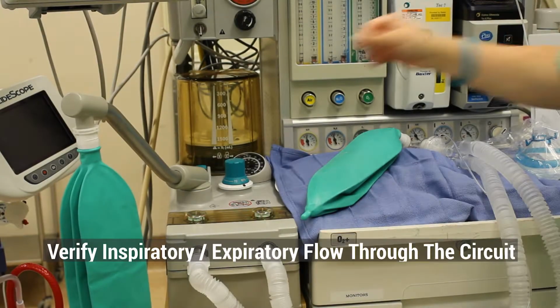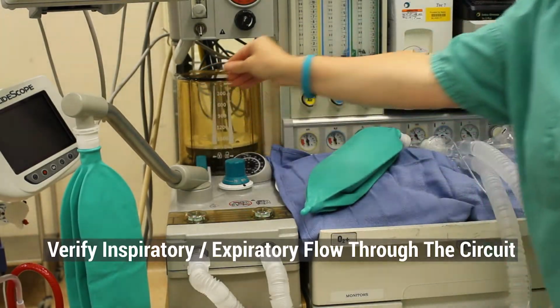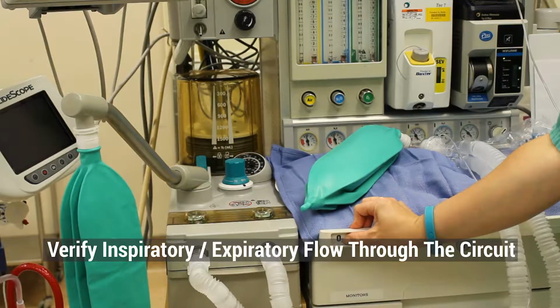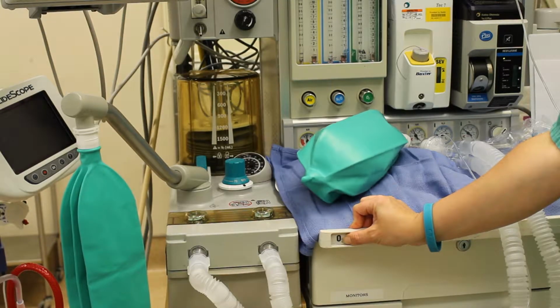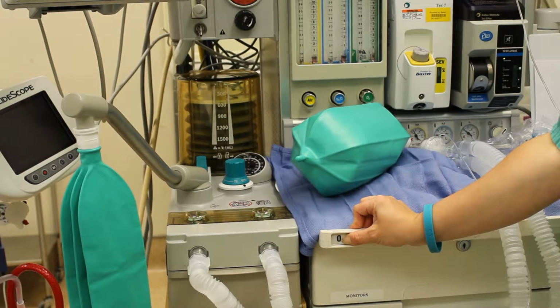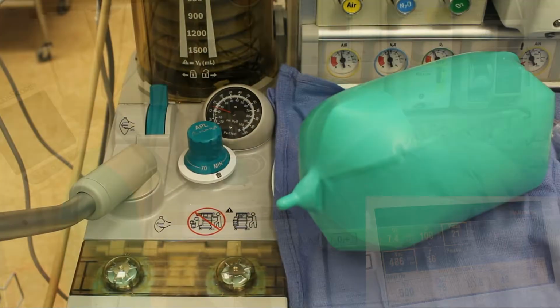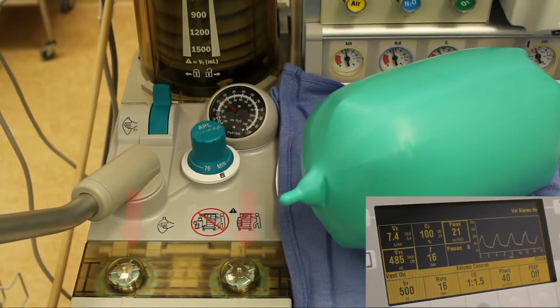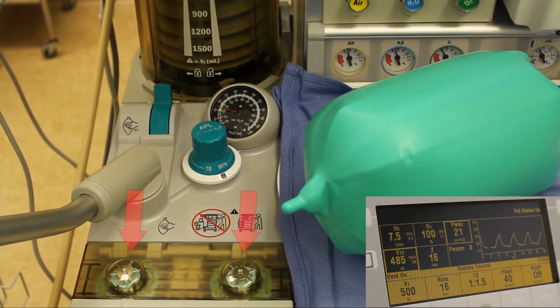Next, verify flow of gas through the circuit during inspiration and expiration. This can be done by using a spare reservoir bag in order to simulate a lung, and is also an easy way to test ventilator function. Check that the inspiratory and expiratory valves move freely, as demonstrated here.